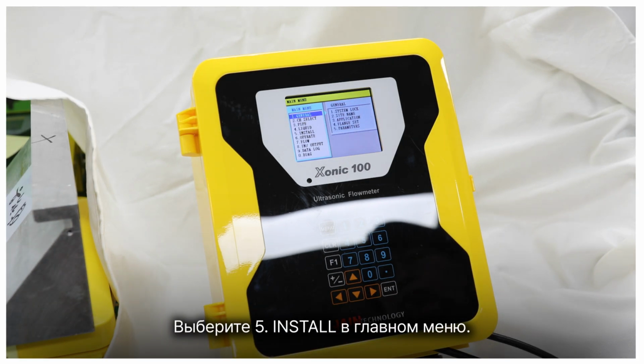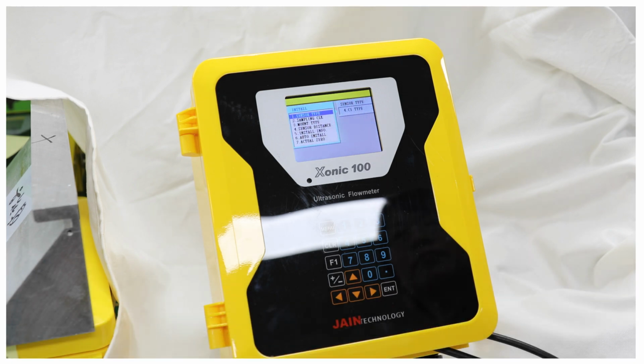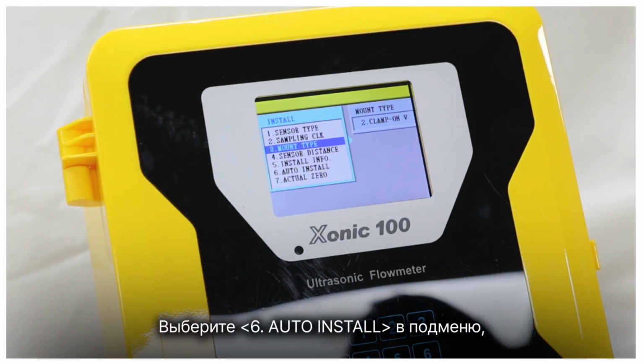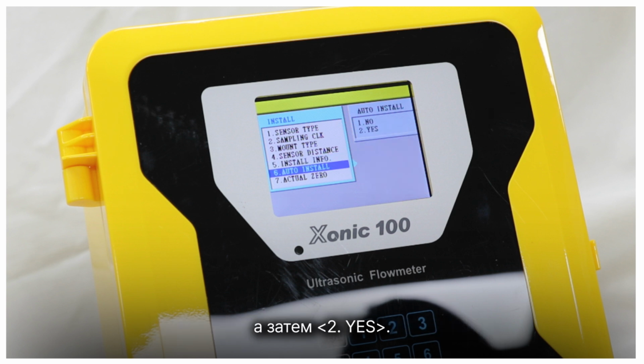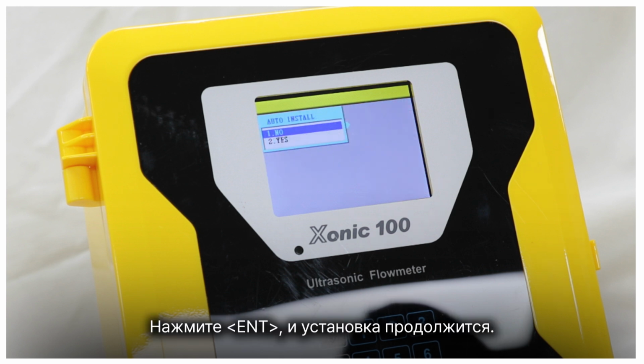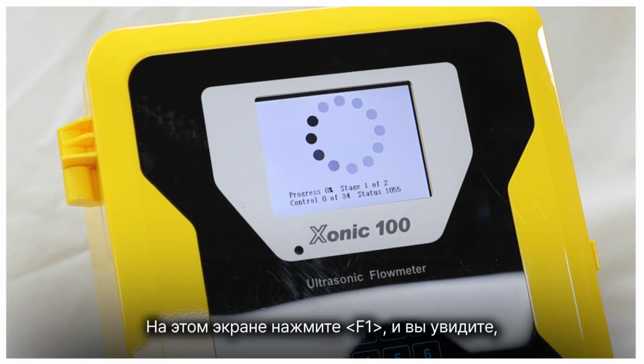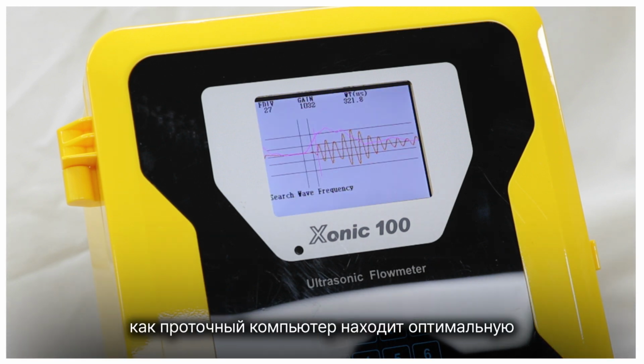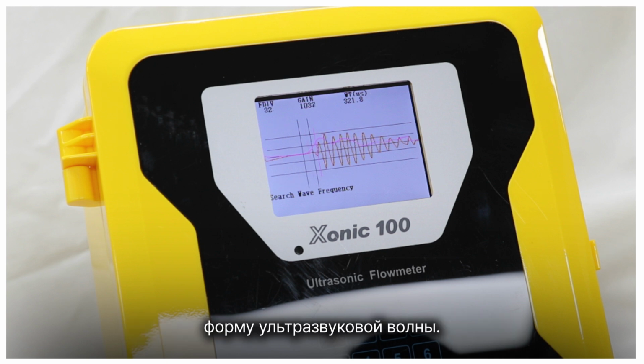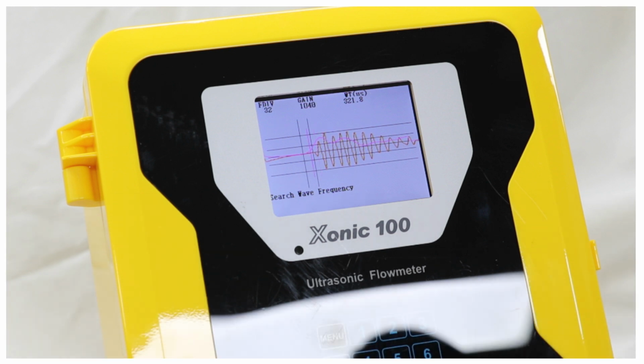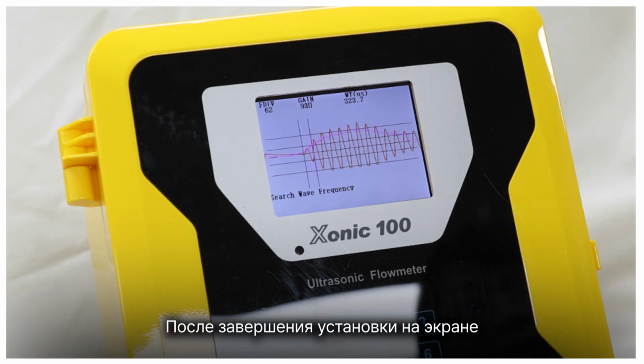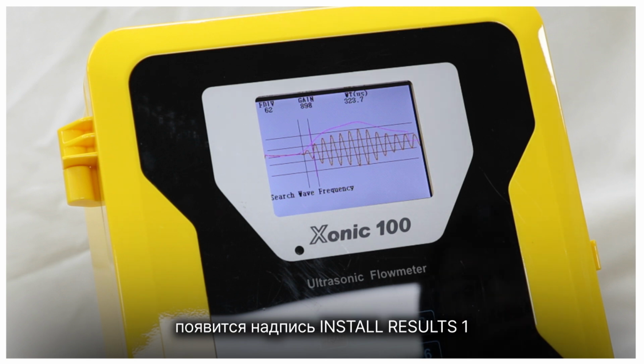Select 5, Install on the main menu. Select 6, Auto Install on the sub-menu, and then 2, Yes. Press Enter and install will proceed. On this screen, press F1 and you'll see the flow computer finding an optimal ultrasonic waveform. When install is complete, you'll see the results on the screen.